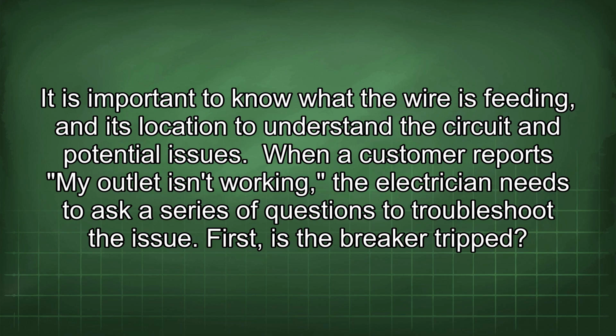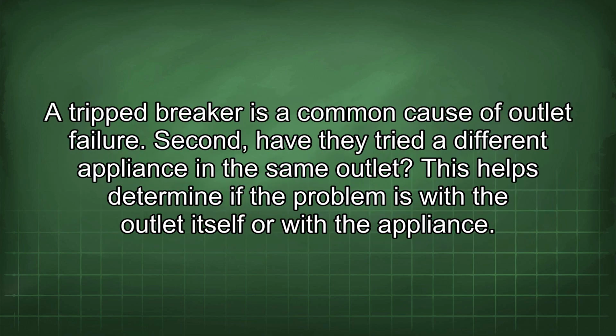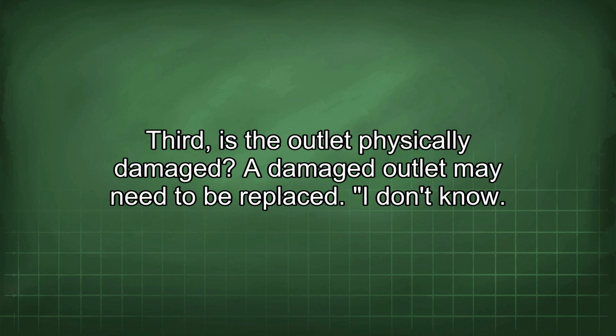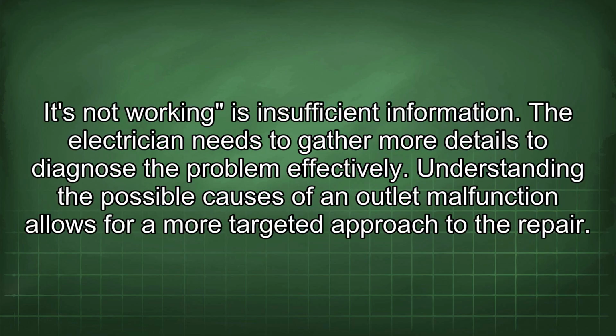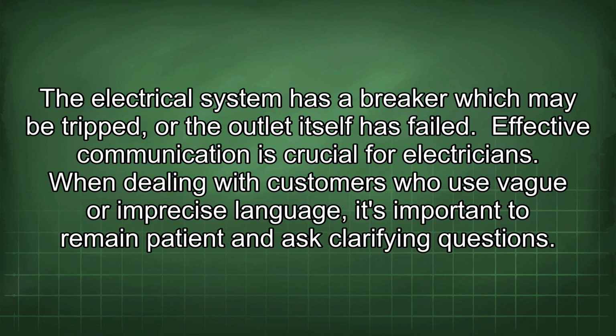When a customer reports "my outlet isn't working," the electrician needs to ask a series of questions to troubleshoot the issue. First, is the breaker tripped? A tripped breaker is a common cause of outlet failure. Second, have they tried a different appliance in the same outlet? This helps determine if the problem is with the outlet itself or with the appliance. Third, is the outlet physically damaged? A damaged outlet may need to be replaced. "I don't know, it's not working" is insufficient information. The electrician needs to gather more details to diagnose the problem effectively. Understanding the possible causes of an outlet malfunction allows for a more targeted approach to the repair. The electrical system has a breaker which may be tripped, or the outlet itself has failed.